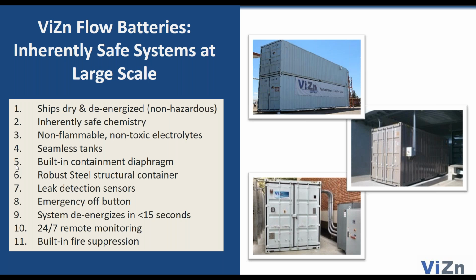Key thing about flow batteries, if you turn off the pumps, you turn off the energy. So we actually have emergency off. If you hit the emergency off button, the electrolyte drains into the tanks, and in 15 seconds, the entire system is de-energized. In case of earthquake, fire, plane crash, terrorist event, whatever, the system can be safely shut down, and it will not discharge energy under any situation. So, you know, these things give us inherently safe systems at large scale. And that is very critical for systems that are deployed at the edge of the grid in residential or urban, suburban areas where the benefit is best of having storage.